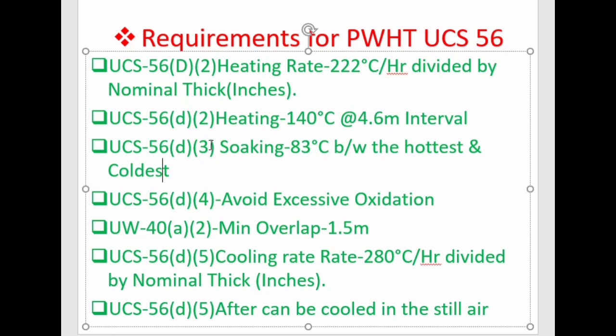During the heating and holding period, the furnace atmosphere shall be controlled to avoid excessive oxidation of the surface of the vessel. If the atmosphere is not controlled, excessive oxygen reacts with the metal surface resulting in rust or metal corrosion. Additionally, the furnace shall be designed to prevent direct impingement of the flame on the vessel — never allow the flame to come into direct contact with the vessel.